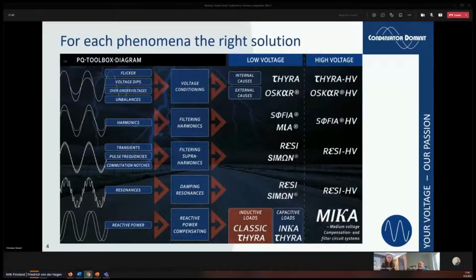The second issue, which is very popular in modern industrial plants, especially where you have a lot of frequency inverters, is classic harmonics. That means you have a 250 hertz, 350 hertz, or in the United States maybe 300 and 420 hertz, or whatever, 5th, 7th, 11th harmonic signal in the grid.